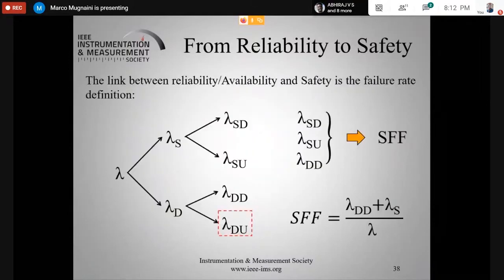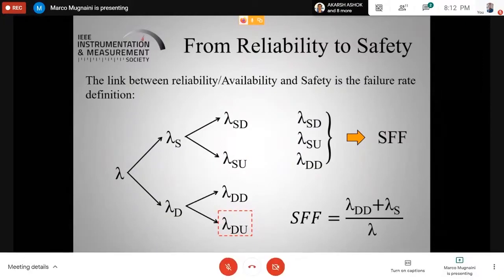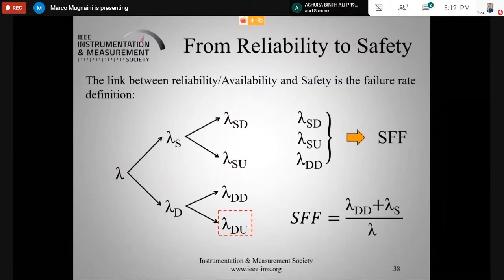What is the peculiarity of this standard? Before, we saw the failure rate for reliability and availability standards. For safety, you have to start thinking that some failures are more severe than others. You can divide them basically into safe failures and dangerous failures. But this is not enough. Then you can think that these failure rates can be divided into detectable safe failures and undetectable, or dangerous detectable, or dangerous undetectable. These latter, in particular, are the ones that determine the safety of a function.